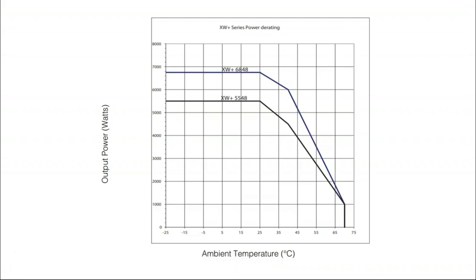Do you have to temperature regulate batteries? I hear that, and I've made it, as an argument in support of lead acid having a larger temperature range than lithium ion, but that's not really true. The truth of the matter is you want to keep your batteries in the most temperature regulated environment possible. The best lead acid batteries I have seen have always been in conditioned, enclosed, dry rooms rather than boxes built off to the side.